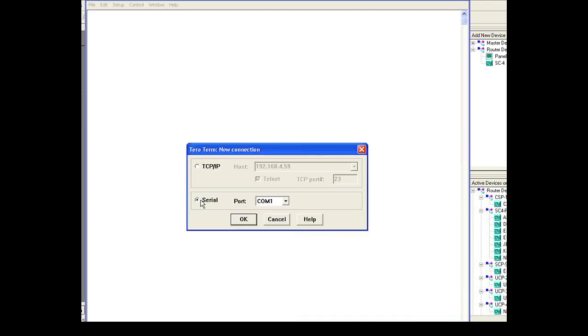You would plug that into that diagnostics port on the active SC4 card. The active SC4 card is the one with the Ethernet lights blinking, if you have Ethernet connected. If you don't, it's the one that has the active LED and most of the LEDs will be lit on it in comparison with the backup. So that will be your active card.